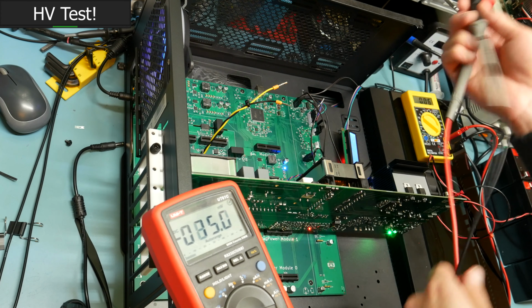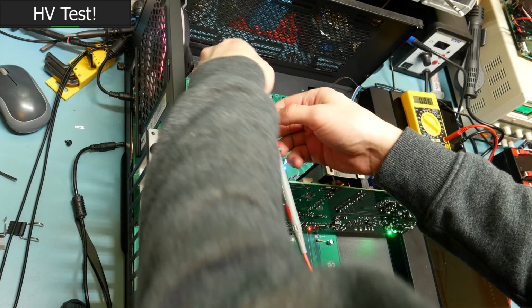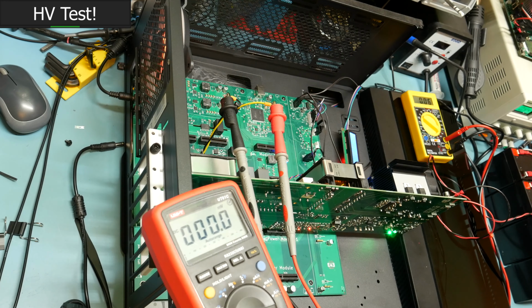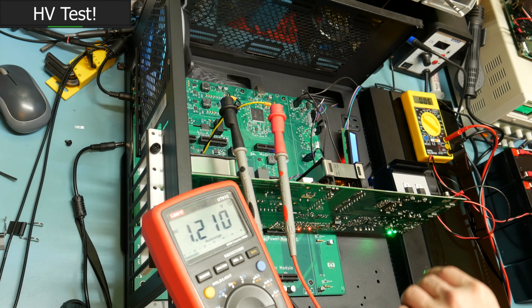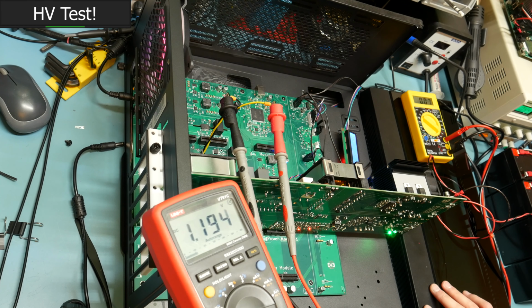So then in order to actually evaluate the high voltage bus, we now have our multimeter hooked up to the bus. And if I hit the go button, it should - I have this thing set up basically with a dead man switch. So if I hold the power button, we should kick on the downstream regulators.